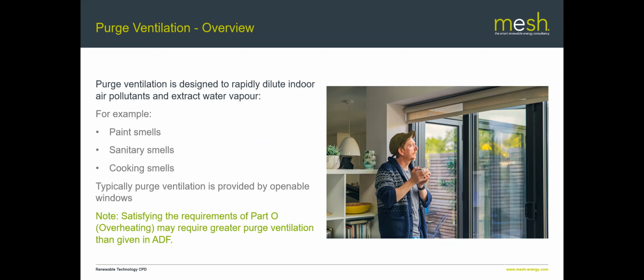Another piece that's worth mentioning is that there's a new Approved Document O, which is overheating, and that also may give rise to a requirement for purge ventilation to prevent or control overheating. And the requirements given in Part O may be higher than in Approved Document F. So you've got three documents you may need to look at for ventilation. You'll certainly need to look at Approved Document F, which is the piece around ventilation in general. Then you may need to look at Approved Document J, which is for the provision of air for fuel burning appliances. And then you may also need to look at Approved Document O for the control of overheating through purge ventilation, and part of that is purge ventilation.